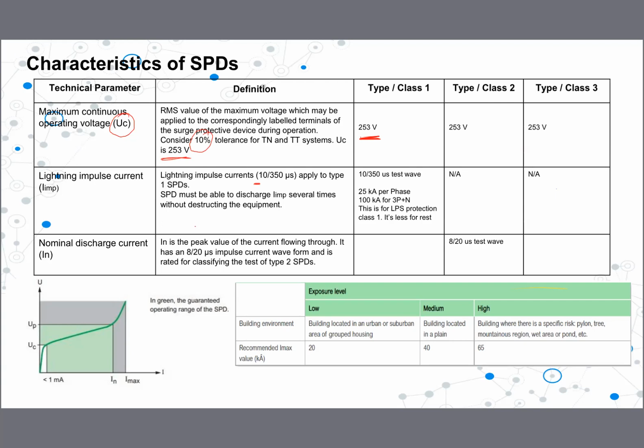Then lightning impulse current, Iimp. Lightning impulse current, this is the wave shape, and this we mostly need for type 1 surge protection devices, because type 1 surge protection devices are the devices we use for lightning impulse protection, right? Then this is the wave shape, right? It is class 1 type, and the current level is 100 kiloampere for 3 phase, and for single phase it is 25, right? And this value also depends on the type of lightning protection class, not the surge protection class, right?